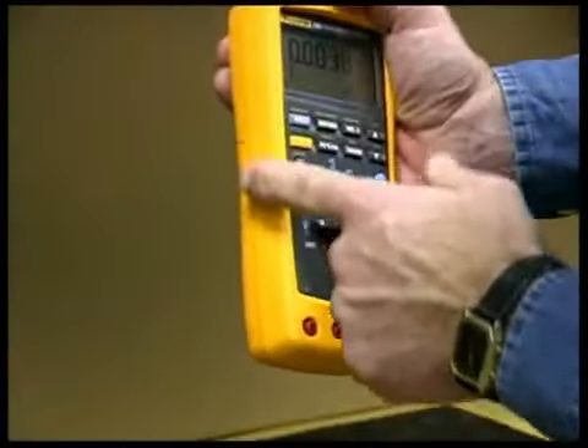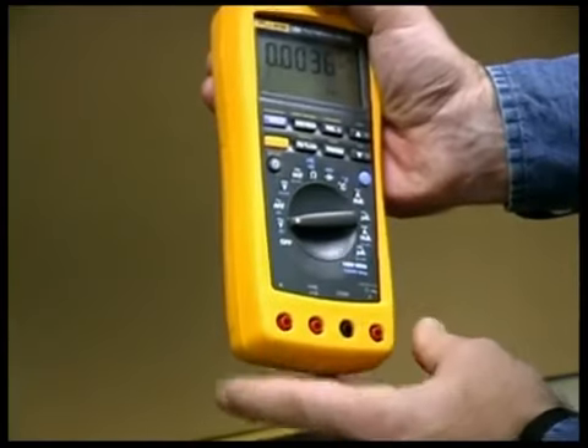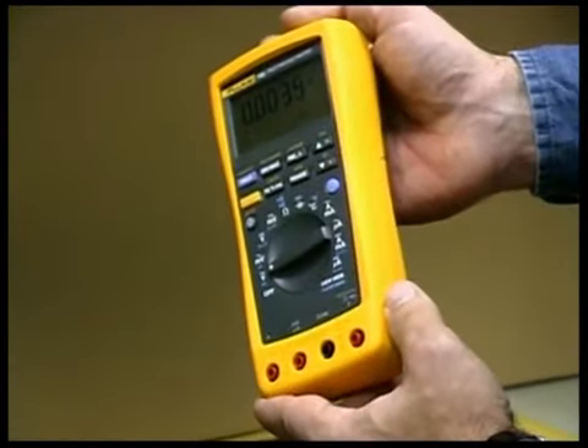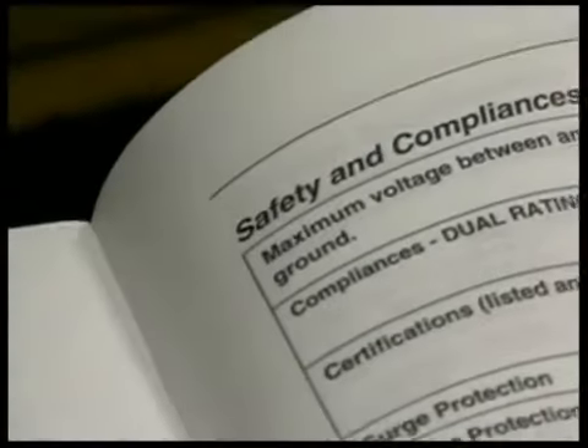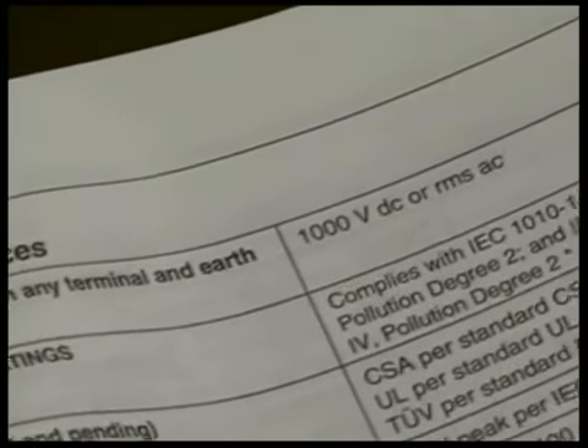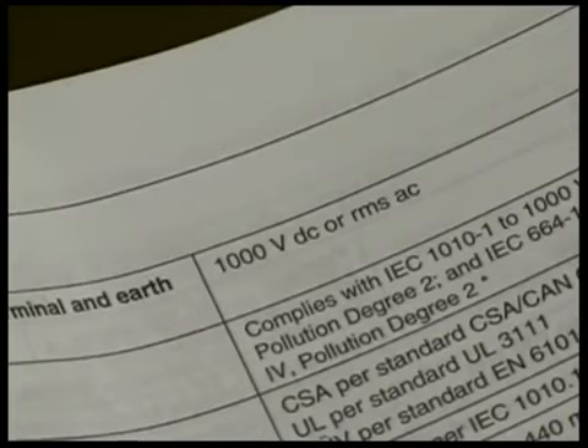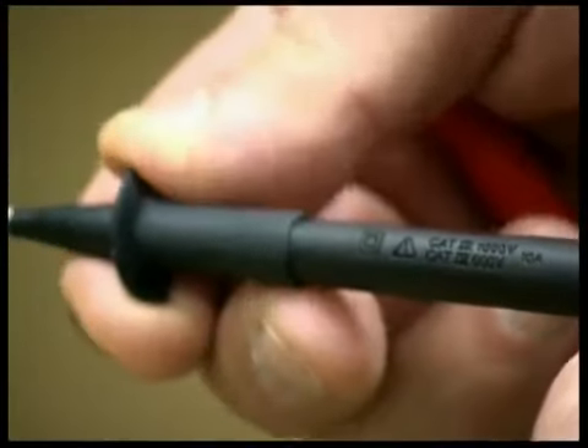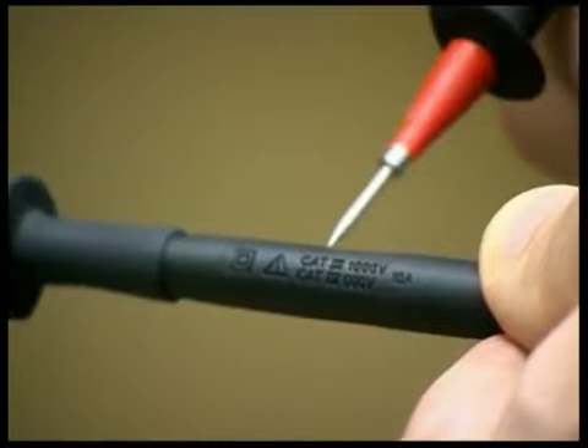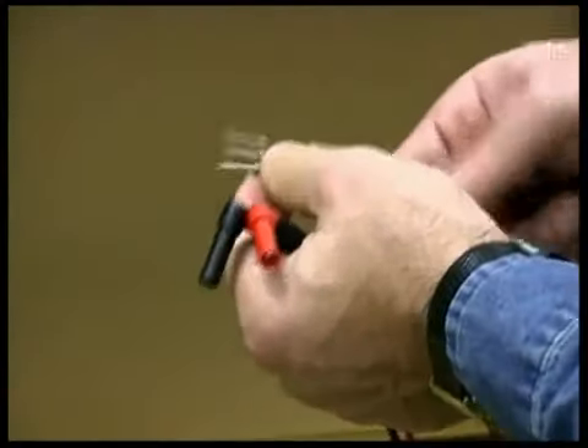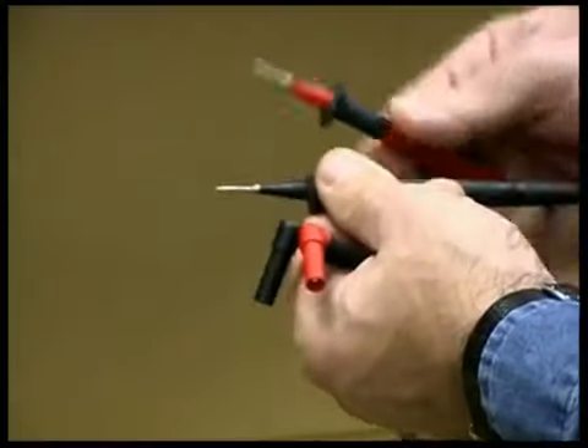Check the condition of your meter. Watch for a broken case, a faded display, or other problems. Check your manual to see if the ohms and continuity circuit is protected to the same level as volts. If not listed, ask for written confirmation from the manufacturer. The relevant standards are covered in IEC 61010. Examine your test leads for finger guards, cat ratings, and double insulation, and look for damages. Check the length of exposed metal.